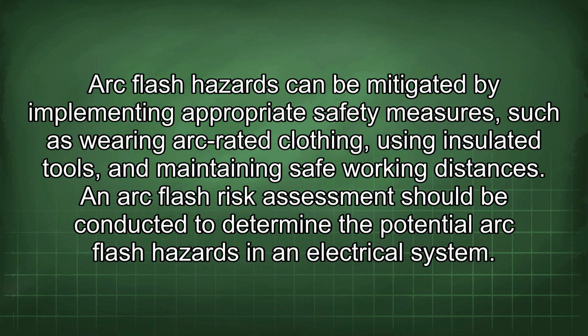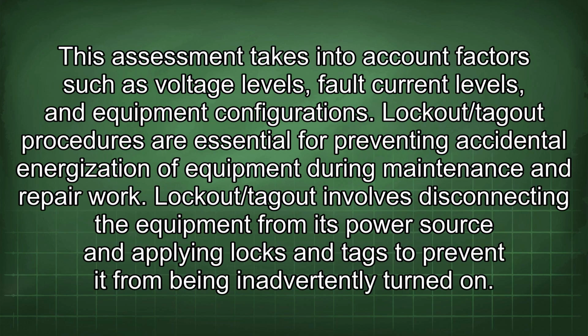Arc flash hazards can be mitigated by implementing appropriate safety measures such as wearing arc-rated clothing, using insulated tools, and maintaining safe working distances. An arc flash risk assessment should be conducted to determine the potential arc flash hazards in an electrical system. This assessment takes into account factors such as voltage levels, fault current levels, and equipment configurations.